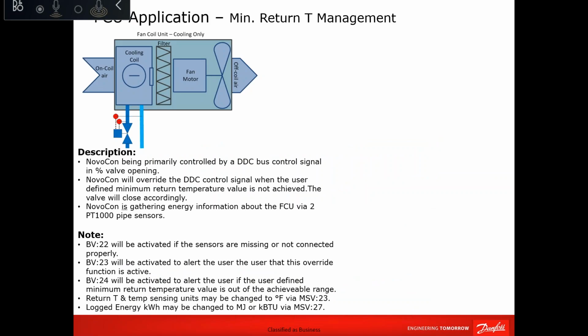So how is it done? It's simple. The Novocon is primarily controlled by DDC or local control, thermostat, 0 to 10 volt, percentage of opening. It will override the DDC control signal when the user-defined return temperature is not achieved. The valve will close accordingly. And the temperature data is gathered from the temperature sensor as well. In the same way, alarms will be there when this is happening. Also, the unit of the energy can be changed: kilowatt, megajoule, and MBH as well.